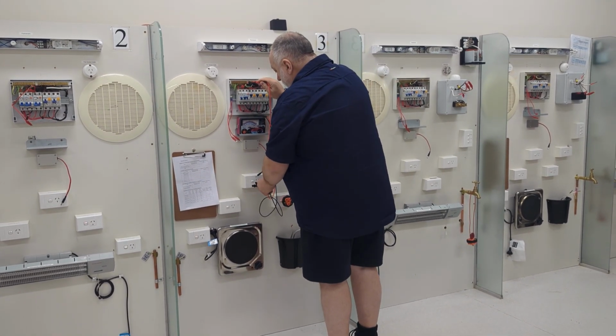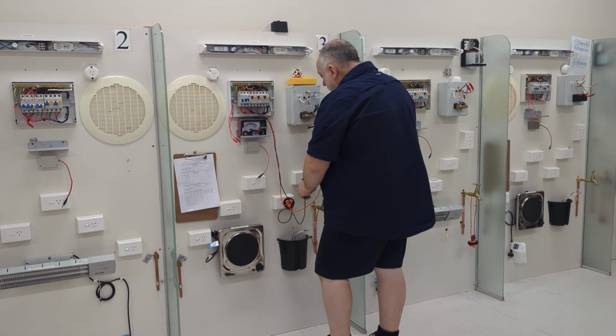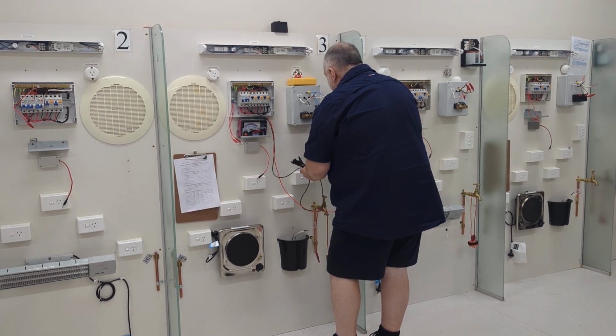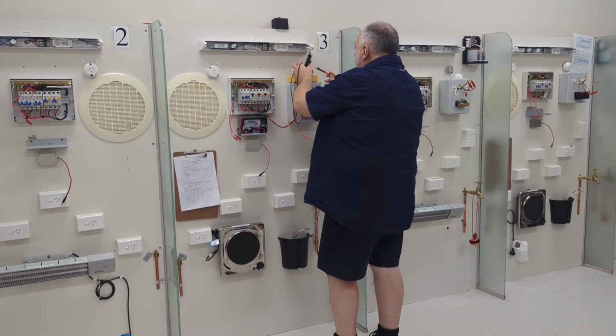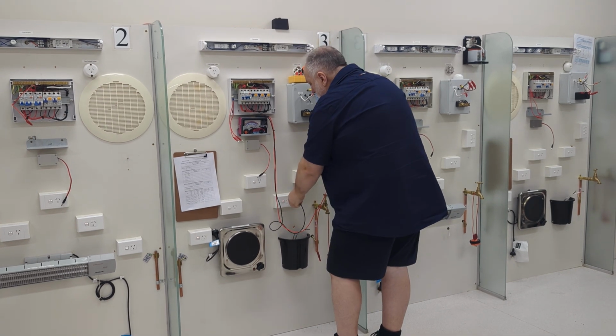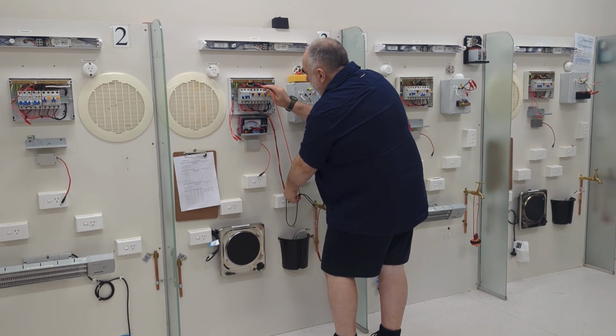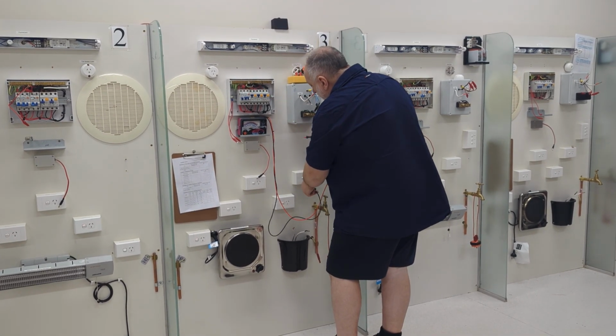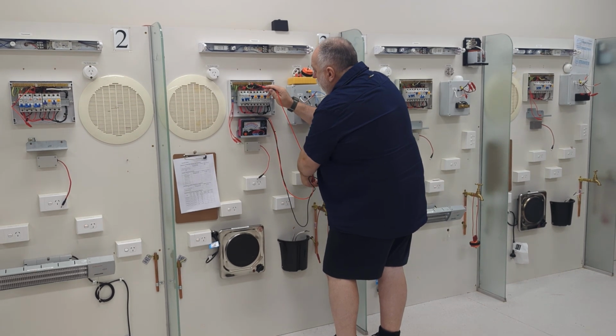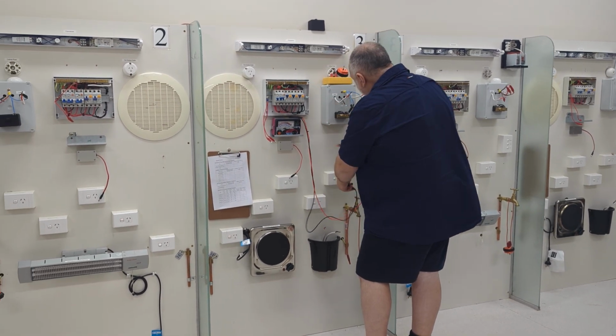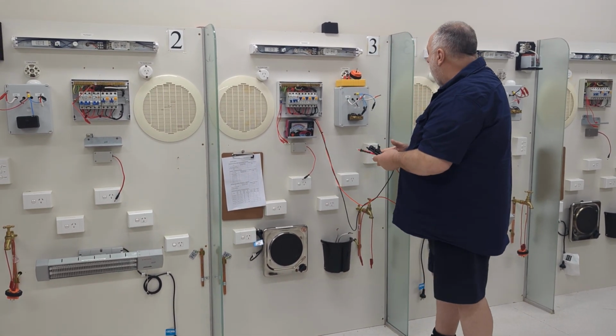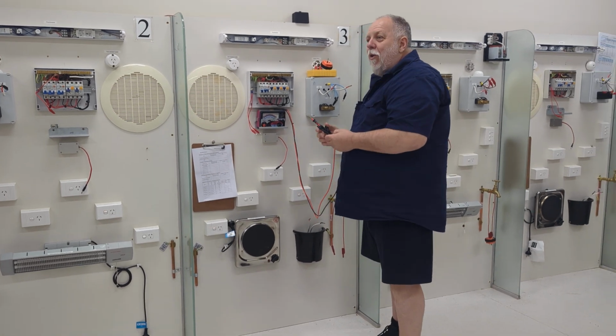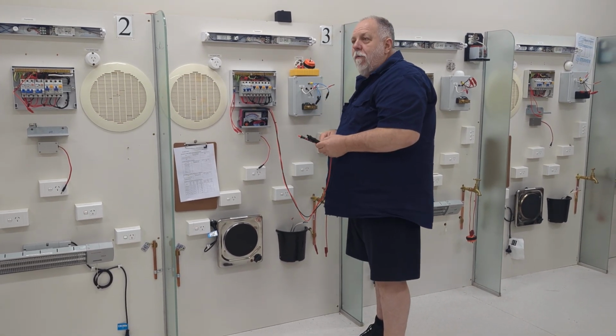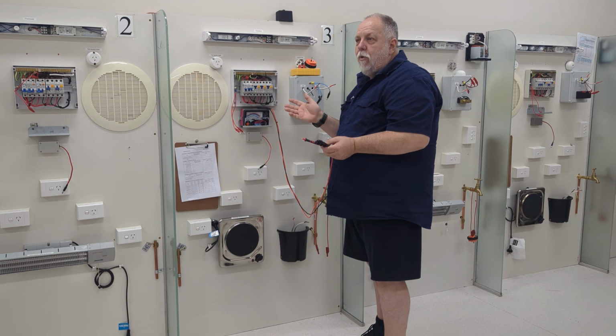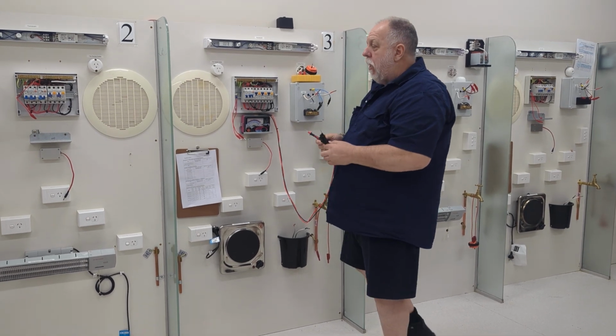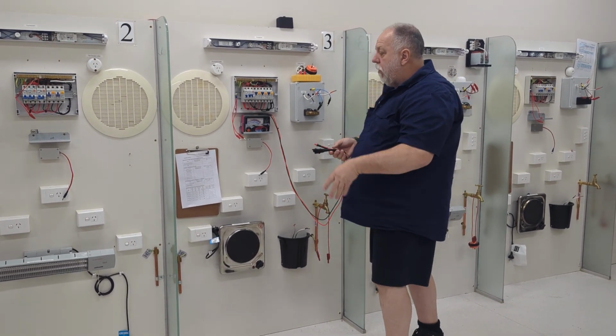I get up to socket number 1. As long as I'm getting a reading, okay. So I'm establishing all my earths up to my earth bar, and I'm getting high readings, more than probably 1 or 2 ohms. So they're going to be ones that are going to fail. Does it make a difference if I have my light switches turned on for doing the earth? No, that's got nothing to do with it. It's only when we do testing of insulation. So I've done all my earths, written them all down.